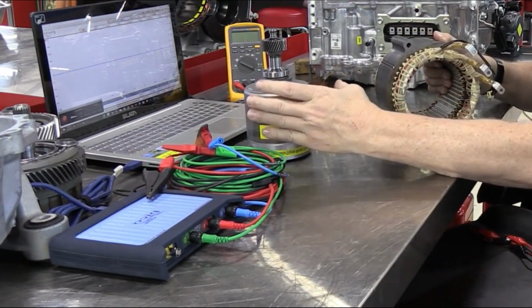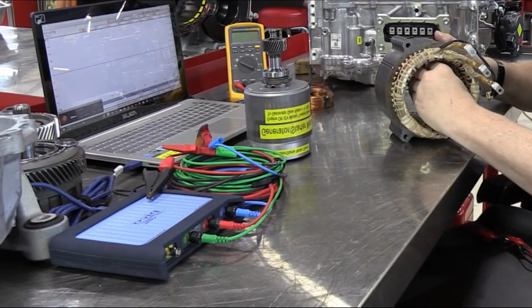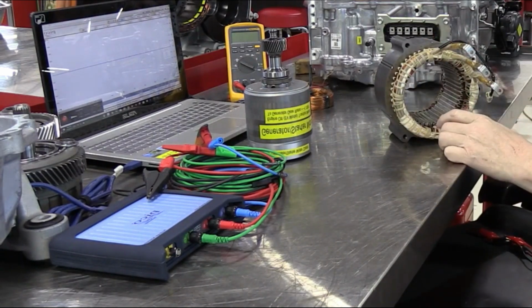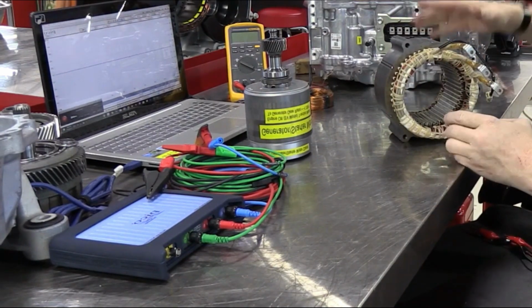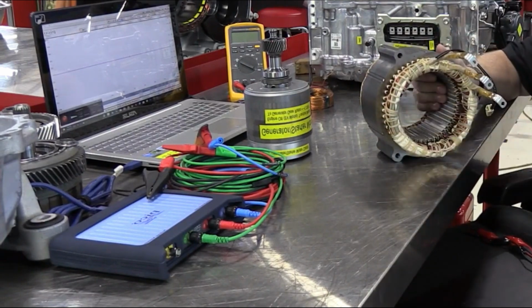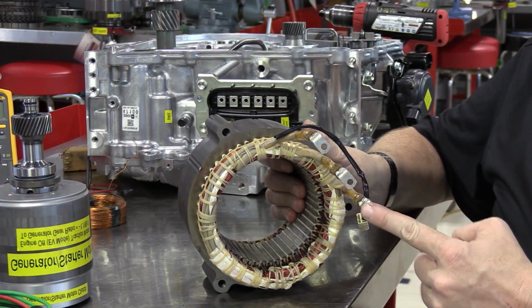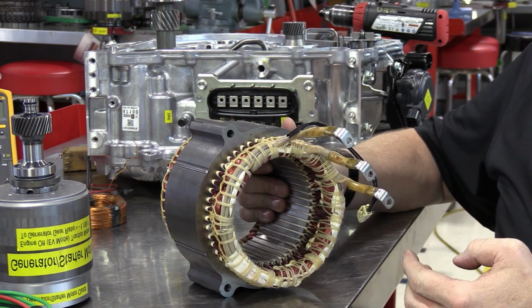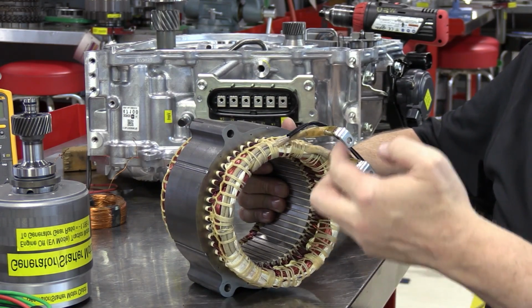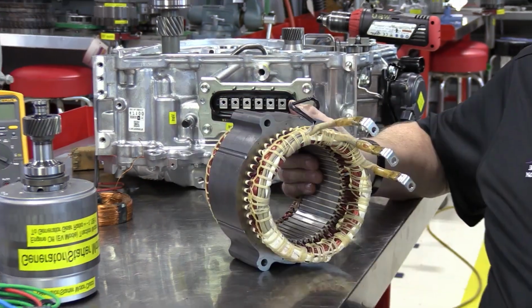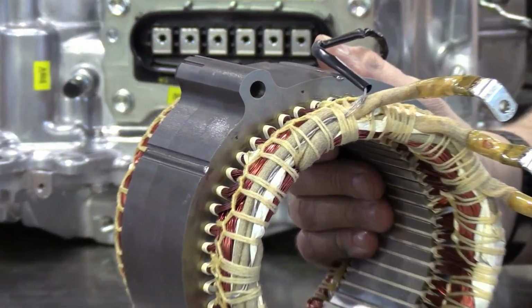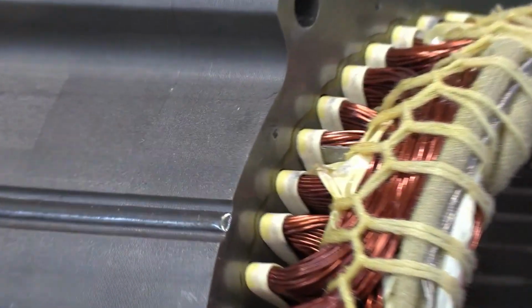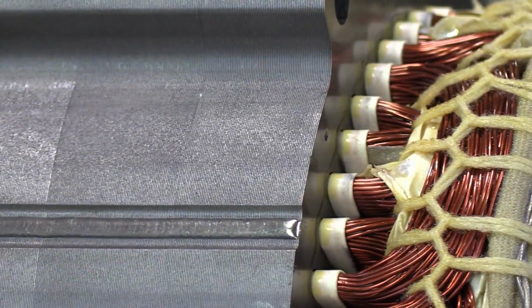Voltage and current analysis: monitor the voltage and current supplied to the motor. Irregularities can indicate issues such as a faulty inverter, wiring problems, or issues with the battery pack. Temperature monitoring: overheating can be a sign of an internal motor issue or cooling system failure. Use temperature sensors to monitor the motor and inverter temperature.